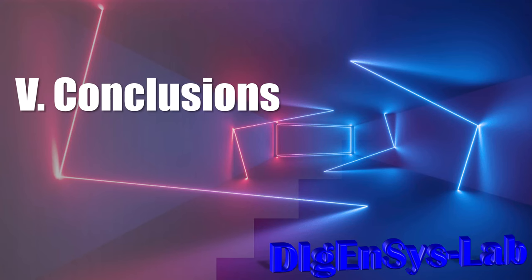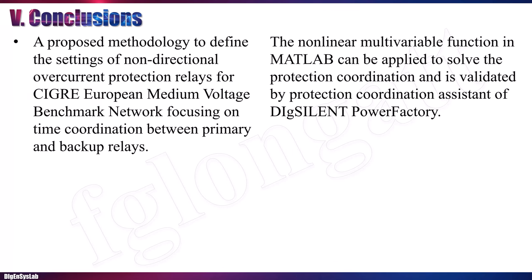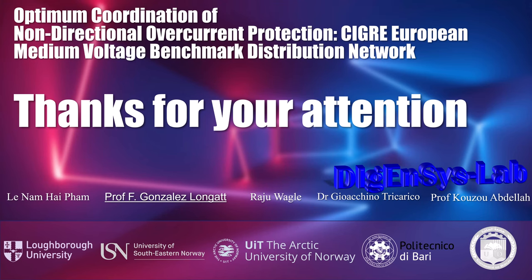In conclusion, this paper proposes a methodology to define the settings of non-directional overcurrent relays using optimization, validated using the CIGRE European Medium Voltage Benchmark Network. The optimization problem is solved using a non-linear multivariable function in MATLAB and compared with DIgSILENT PowerFactory. The conclusion is that there is only a minor discrepancy between results, providing proper coordination for non-directional overcurrent. Thank you for your attention — it's time for questions and answers.